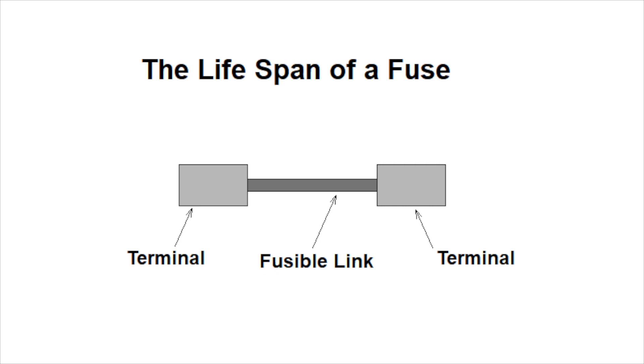The fuse rating is not the current at which it will fail it is a current at which it will operate. Therefore a 20 amp fuse will pass current at 20 amps without damage and will fail at some point above 20 amps.